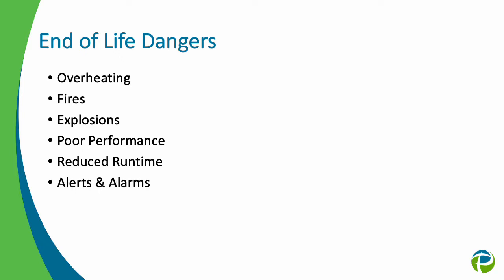And then alerts and alarms. So the last thing you're going to see is as your system starts getting to its end of life and not performing correctly, you'll see poor performance and reduced runtime. Hopefully you don't see overheating, fires, and explosions, but you can. Your system is going to start alerting and alarming—there will be components and parts of the systems that need replaced, serviced, maintained, looked at. So you want to be very cognizant of alerts and alarms, which we always recommend monitoring for any critical facility system.